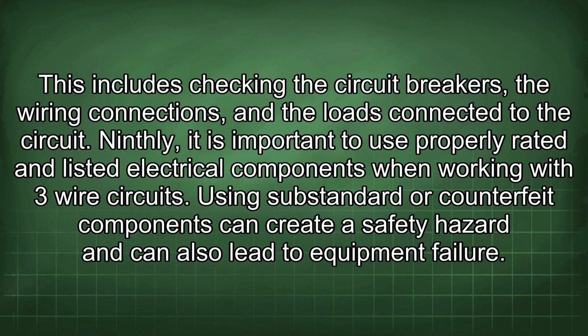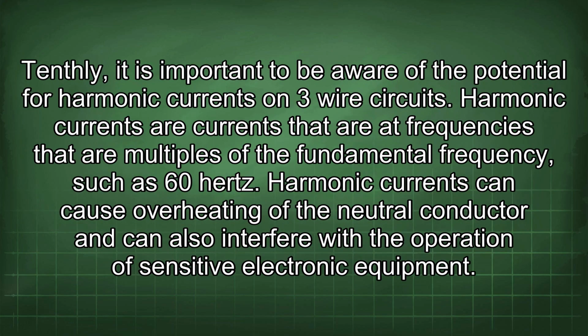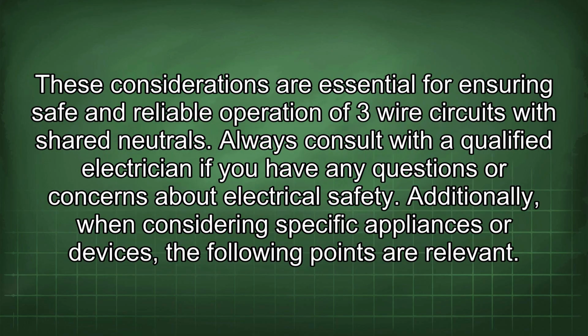Using substandard or counterfeit components can create a safety hazard and can also lead to equipment failure. Tenthly, it is important to be aware of the potential for harmonic currents on 3-wire circuits. Harmonic currents are currents that are at frequencies that are multiples of the fundamental frequency, such as 60 Hz. Harmonic currents can cause overheating of the neutral conductor and can also interfere with the operation of sensitive electronic equipment. These considerations are essential for ensuring safe and reliable operation of 3-wire circuits with shared neutrals. Always consult with a qualified electrician if you have any questions or concerns about electrical safety.